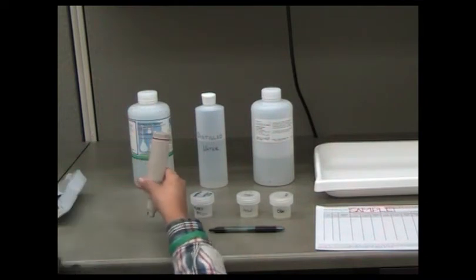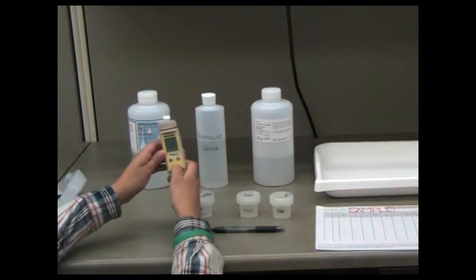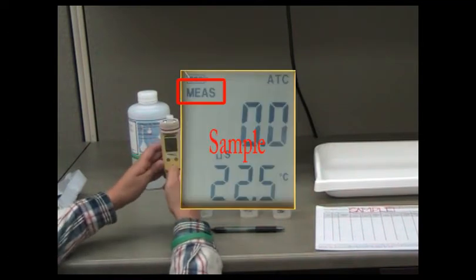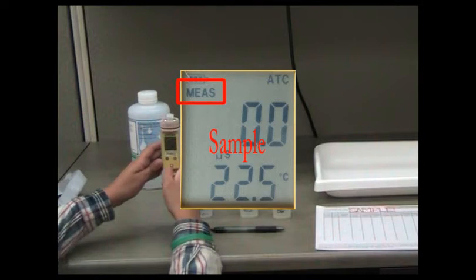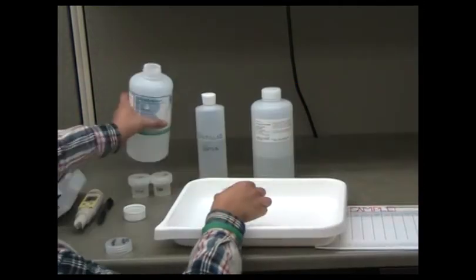Turn on the EC tester and make sure that the tester is in measuring mode. The letters MEAS should appear at the top of the screen. If these letters do not appear, use the mode button to toggle to measuring mode.